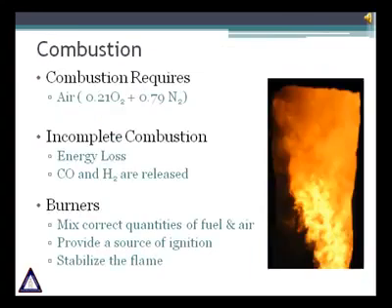Combustion is an exothermic reaction resulting from a rapid combination of oxygen with fuel. Since perfect mixing of fuel and air is not possible, excess air is needed to ensure complete fuel combustion. For every part of oxygen, 4 parts of nitrogen enter the combustion process and leave without reacting. The N2 absorbs some of the heat and carries it to the stack. It is necessary to minimize excess air to avoid excessive heat loss.